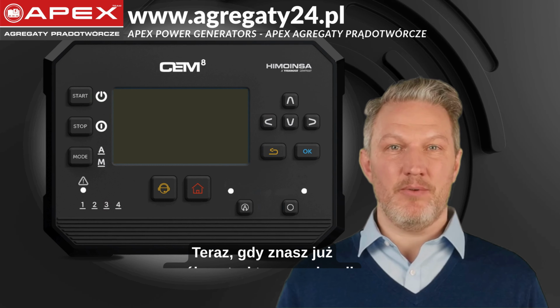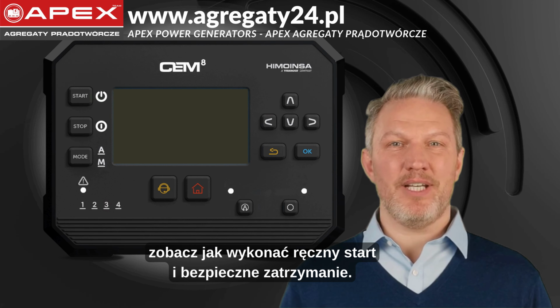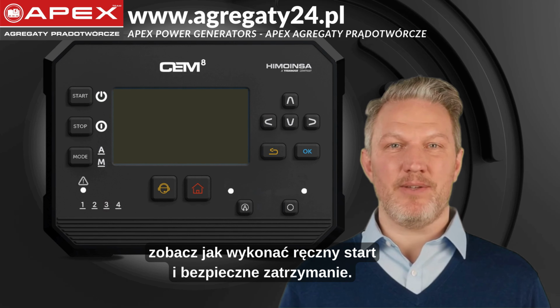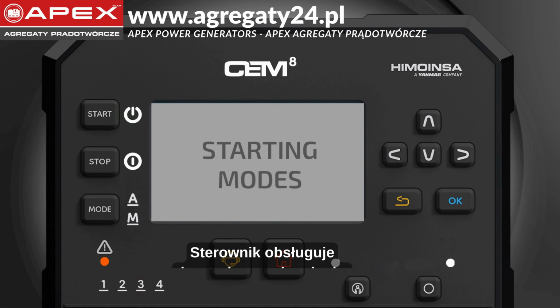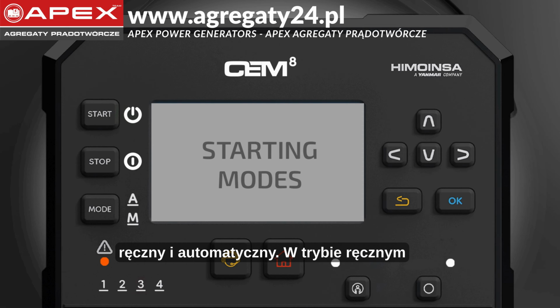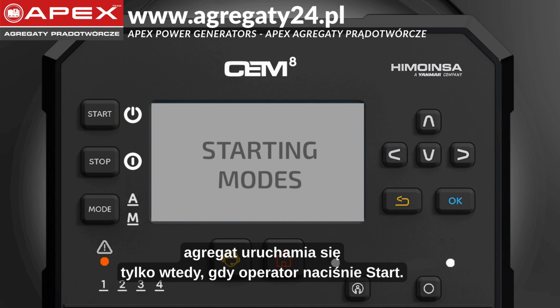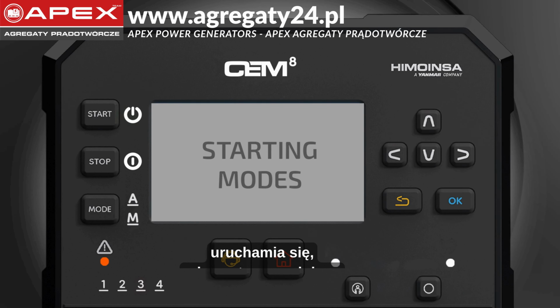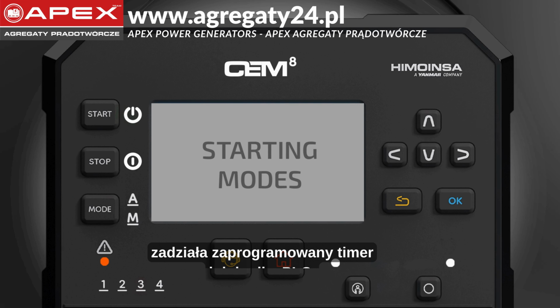Now that you know the overall navigation structure, let's look at how to perform a manual start and a safe stop. The controller supports 2 start modes, manual and automatic. In manual, the generator starts only when the operator presses start. In automatic, it starts when preset conditions are met, an external signal, a scheduled timer, or PLC logic, without touching the panel.